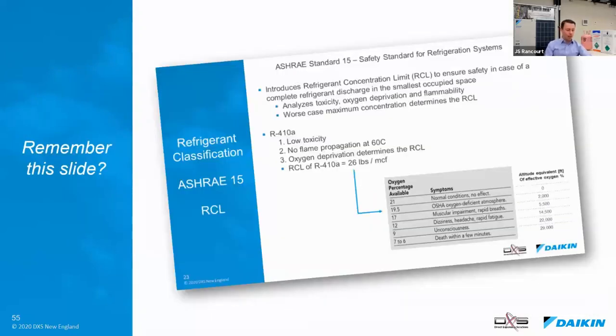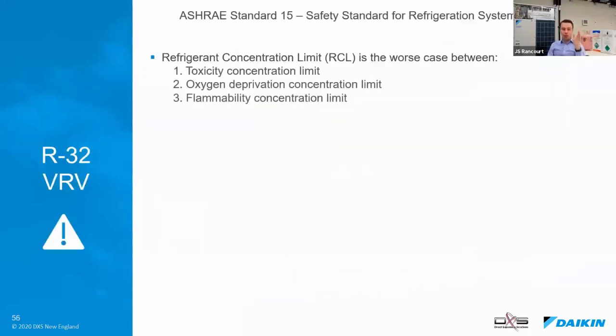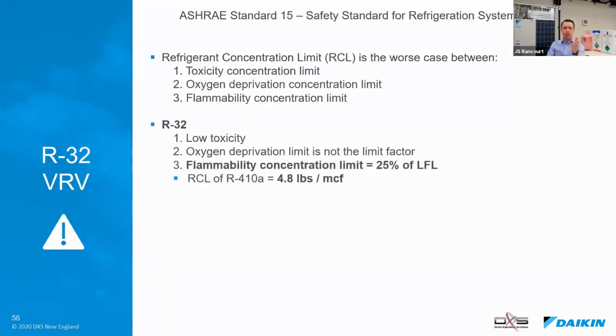So one last comment here. I'll finish in 1 minute and open up the Q&A. If you remember our ASHRAE 15 limit on RCL, I'm gonna raise a little warning here on R32. Remember, RCL looks at the worst of toxicity, oxygen deprivation, and flammability. And now that we have R32, oxygen deprivation is no longer the limiting factor, but it is the flammability concentration limit.